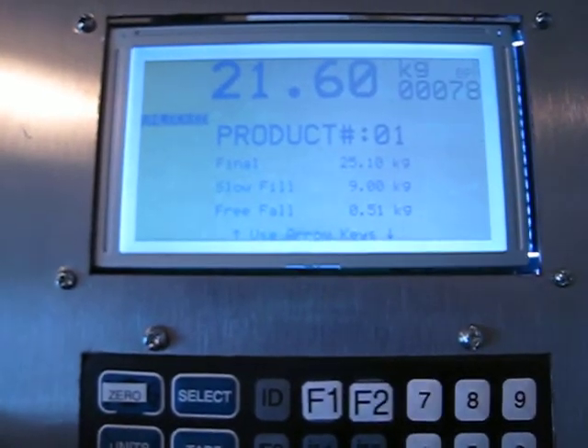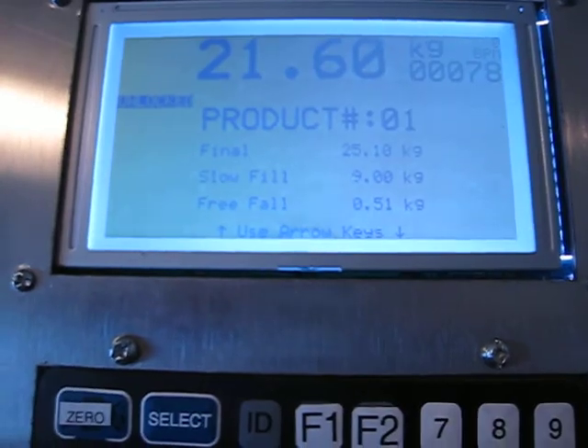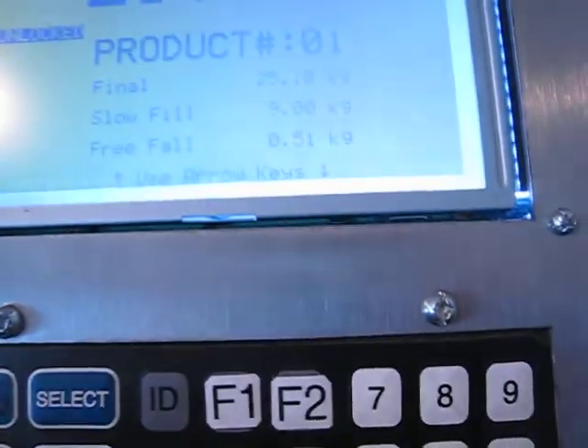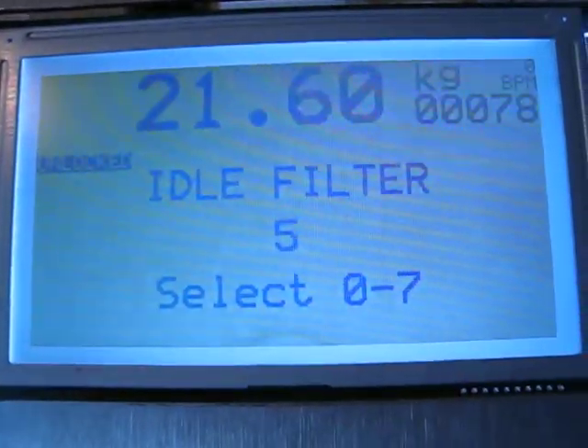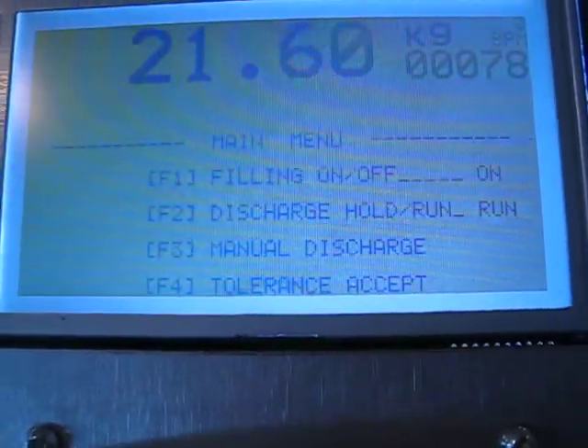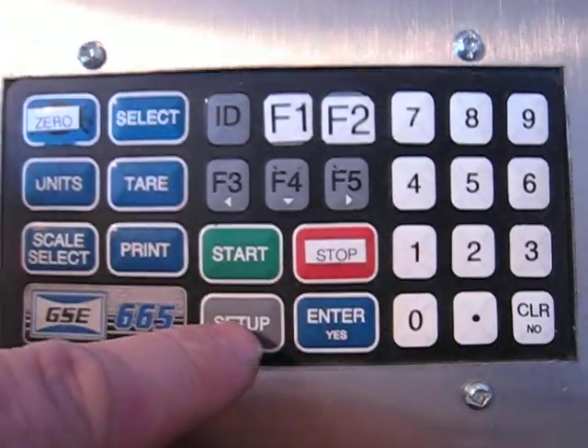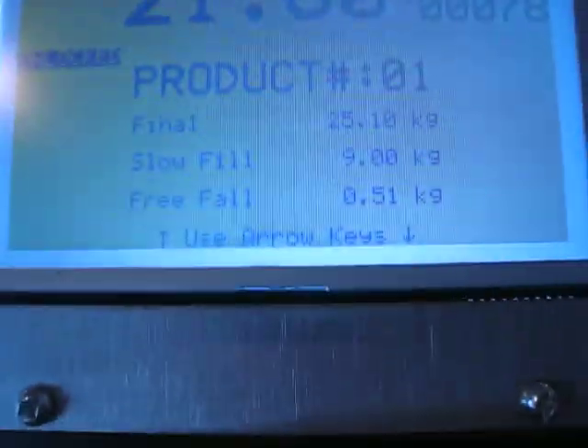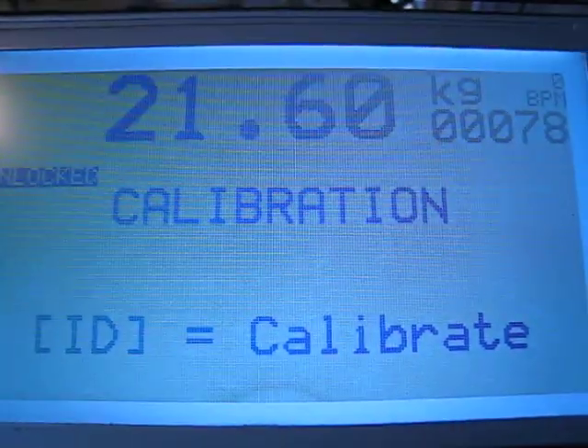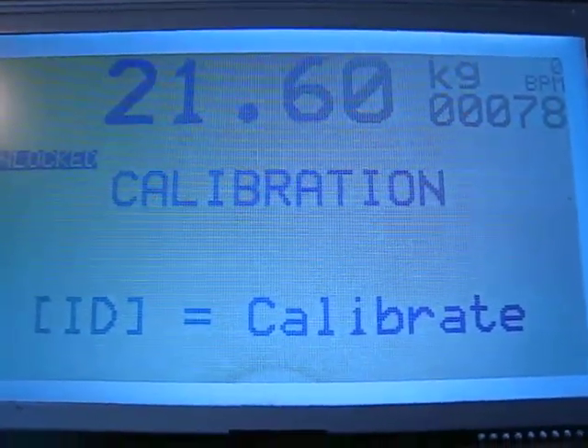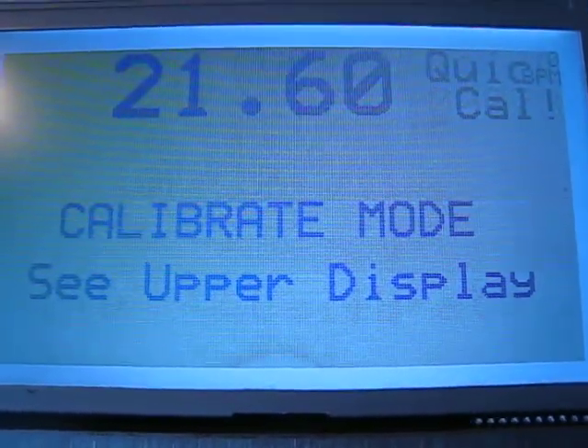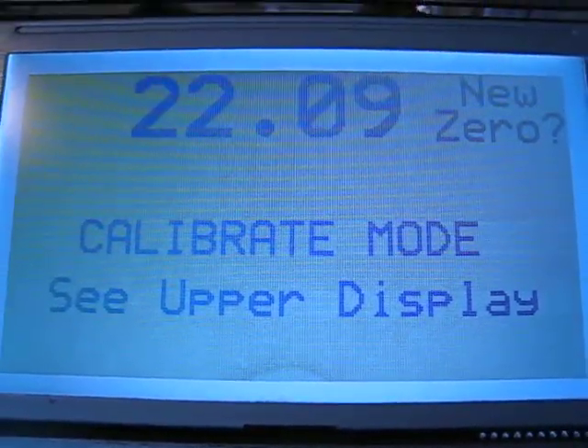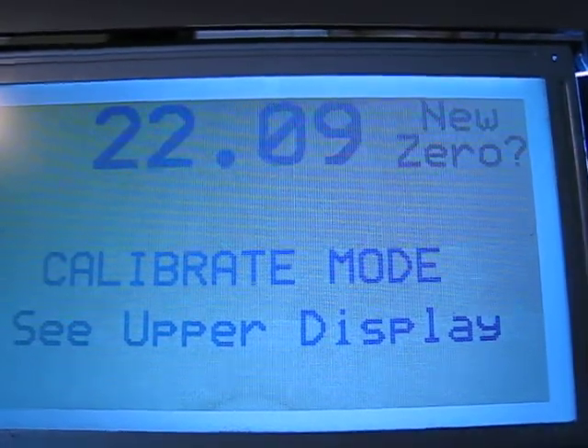Going to review some additional higher end features on the 663 control panel. If we hit the setup button here and then we arrow down, so we'll just exit here. So setup button, and then if we use F4 and arrow down, we come to essentially the last parameter, which is the calibration. So if we push ID here, it will start stepping us through the calibration mode.